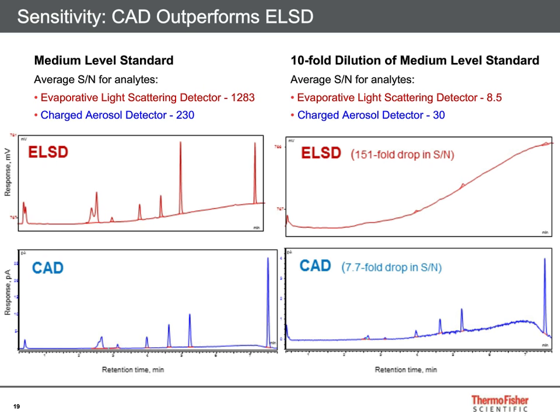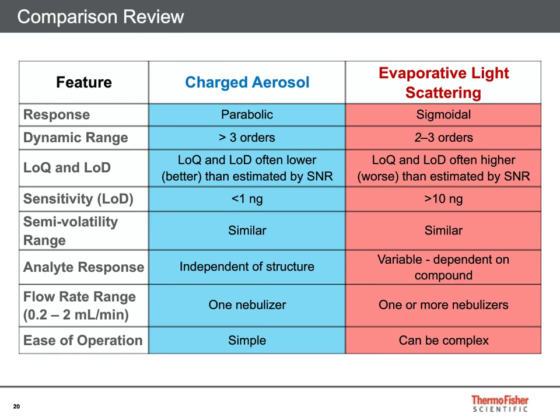To summarize the performance differences: ELSD signal response is sigmoidal, which adversely affects quantitative accuracy, uniformity of response, and sensitivity. The charged aerosol detector exhibits a parabolic signal response that does not sharply fall off at the low end as happens with ELSD. This gives the charged aerosol detector good sensitivity at 1 nanogram or below and a dynamic range exceeding three orders of magnitude.